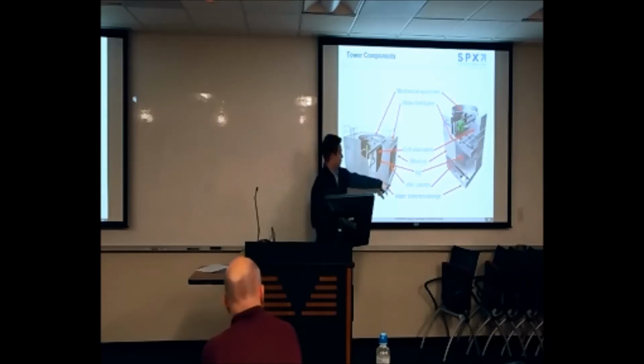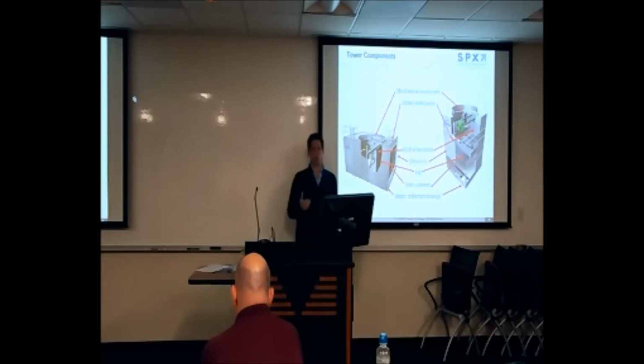Then at the bottom, the water will travel down the fill, get cool, and reach a water collection basin, or what we call a cold water basin, is another term for it. This is where you'll have a lot of your liquid level controls, and this is where the water will be pumped out to the rest of the system. So it is a pretty simple machine, but there's also a lot to consider from a maintenance standpoint.